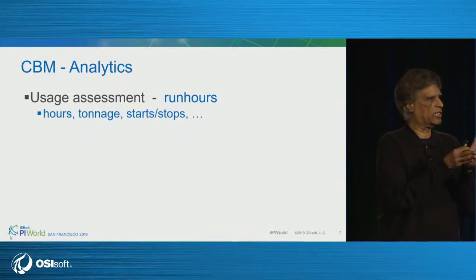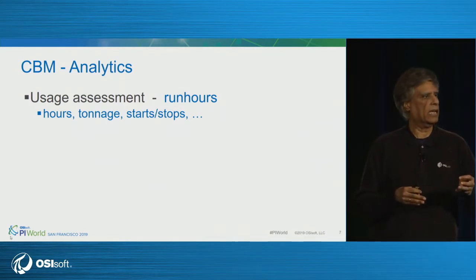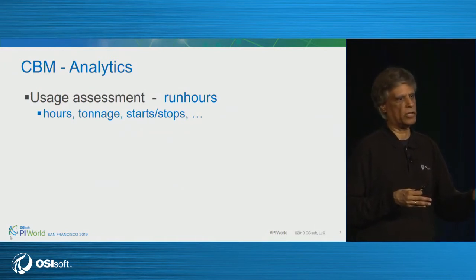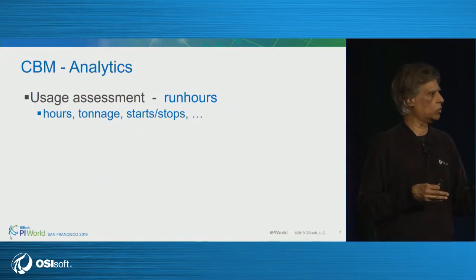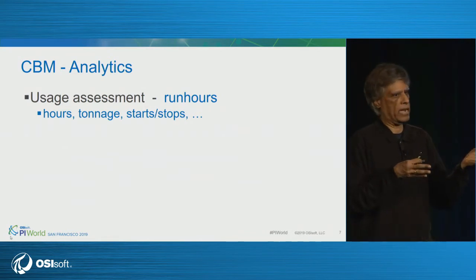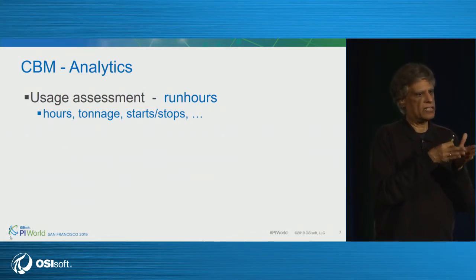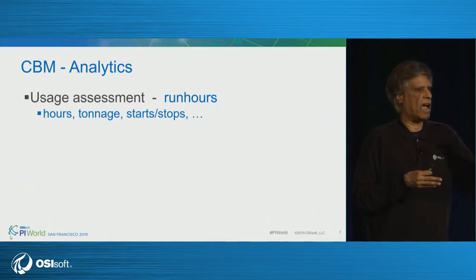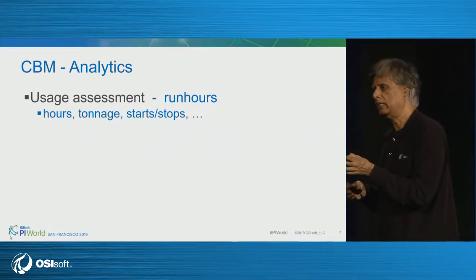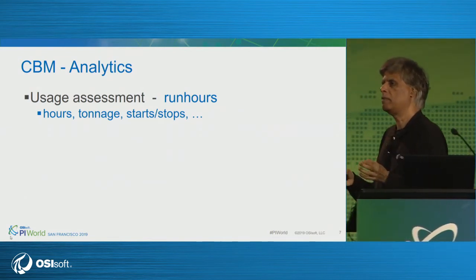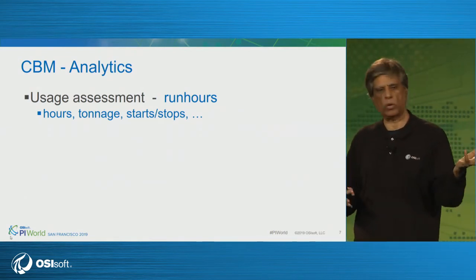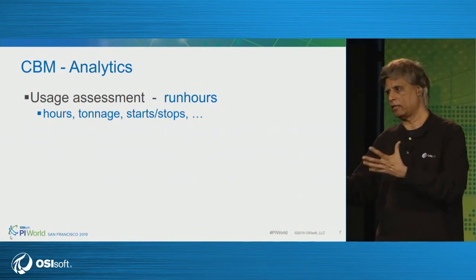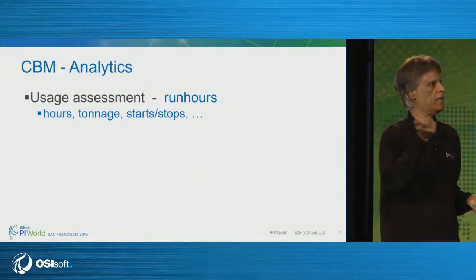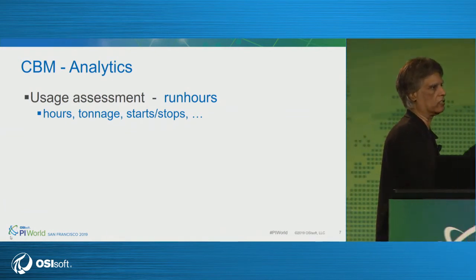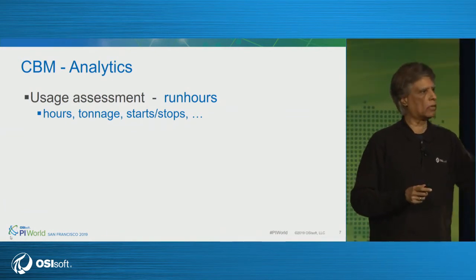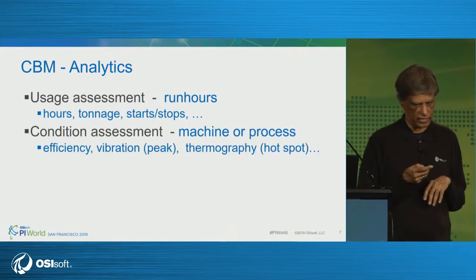Run hours is just a generic term. It could be the amount of coal crushed by your pulverizer, or the amount of fluid flowing through a pump — anything you can use to assess usage. It doesn't even have to be an indicator from your SCADA system; it can just be a proxy. For example, the amperage on a motor can tell you whether the pulverizer is running or not, even if the SCADA itself has no status indicator for running or idle. There are other proxies you can use for usage assessment.